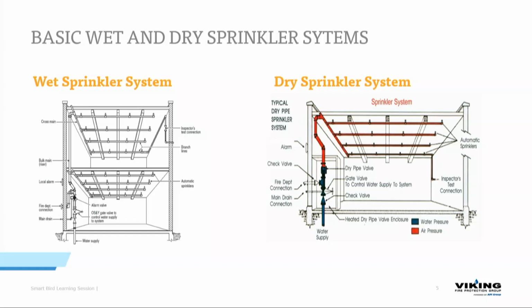Dry sprinkler system, a little bit different components, mostly up here in the valve assembly. We do still need a heated enclosure for that water supply to come into the building. These pipes right here that are red are full of air. They're backed up by an air compressor. That air compressor holds back a clapper in a dry valve until that air is released. Typically that would be a fire fusing one of the links on the sprinkler heads. The air goes out, the clapper opens up, water comes in. Again, we have an inspector's test on the end, and there's a time delivery for dry systems. The key to a dry system in any building is about 40 degrees ambient temperature. That's what the code is going to say.